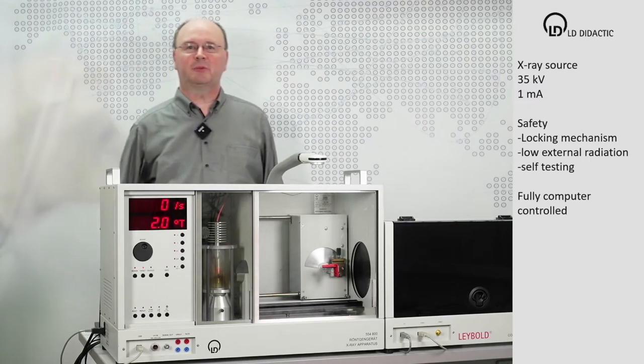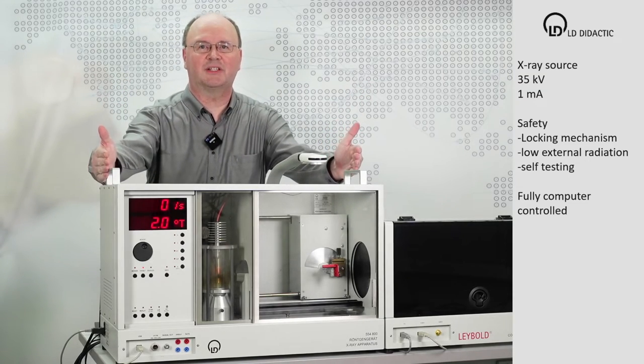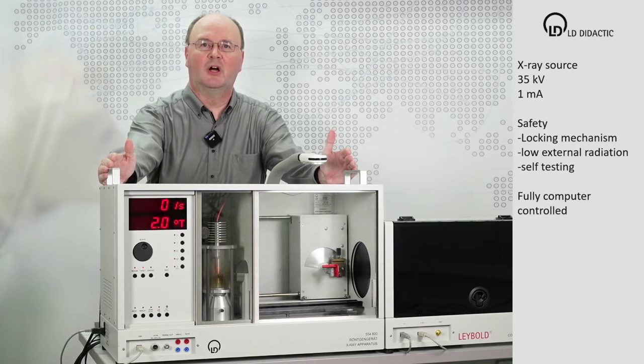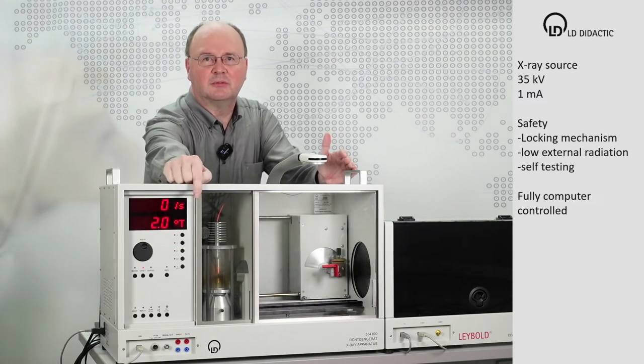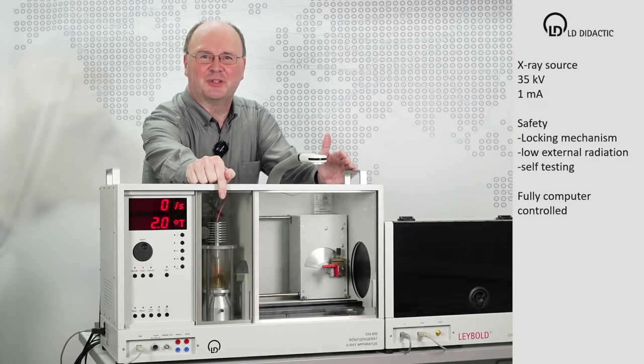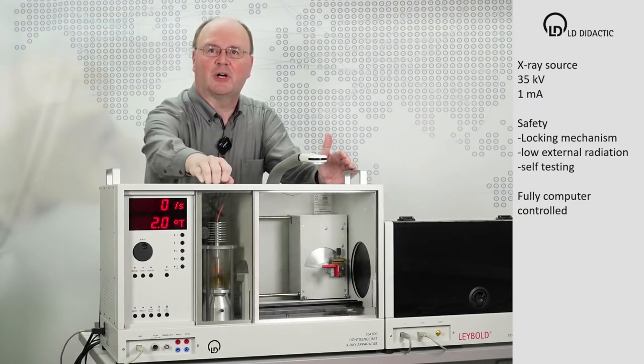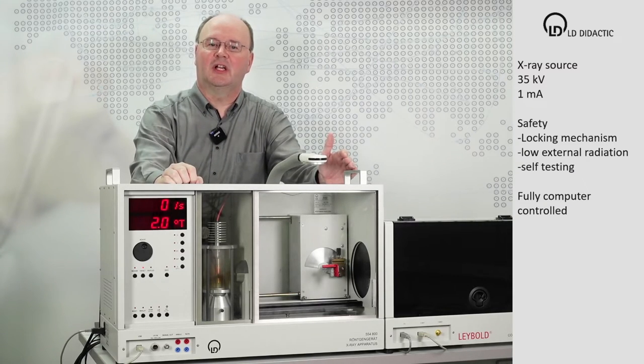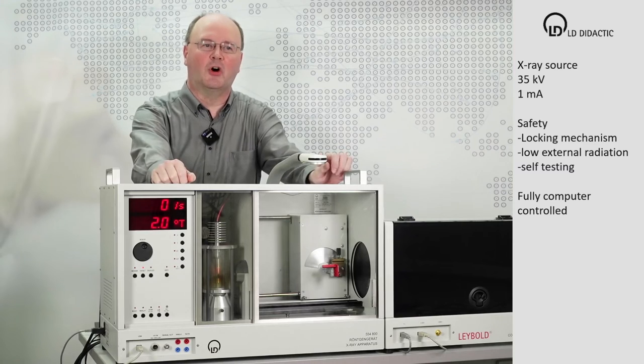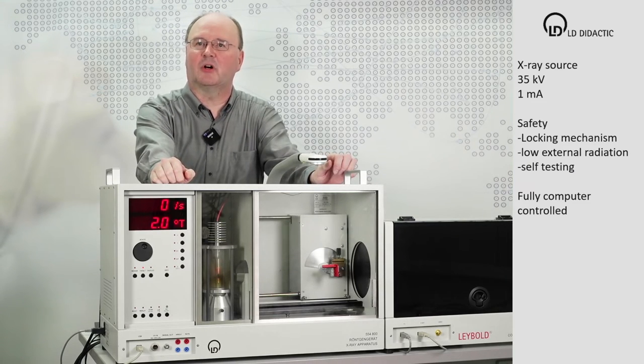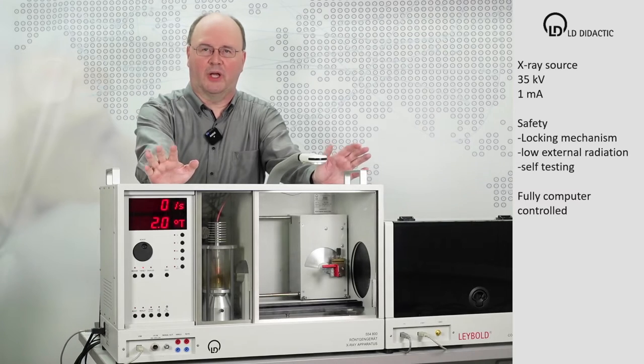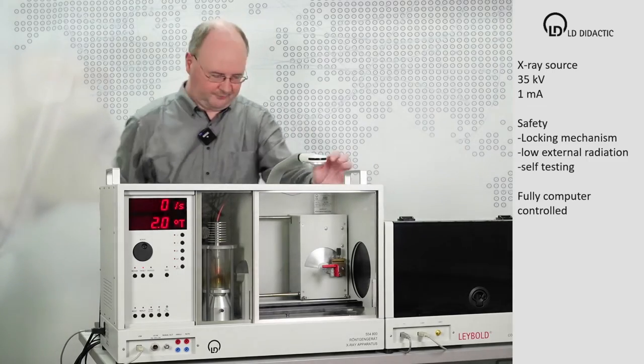Talking about the X-ray machine, this from my left hand to my right hand is the X-ray machine itself. We have an X-ray tube here underneath my finger, where the X-rays are produced, 35 kV, 1 milliamp. It's not that much, but it's absolutely sufficient to do all the experiments we'll talk about. For safety reasons, everything is shielded here. There is no radiation leaking to the outside. We're talking about microsieverts per hour where I'm standing. So it's absolutely safe. There is a locking mechanism, and you hear it when I close the doors.